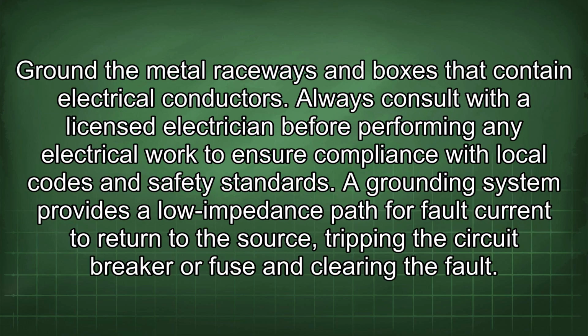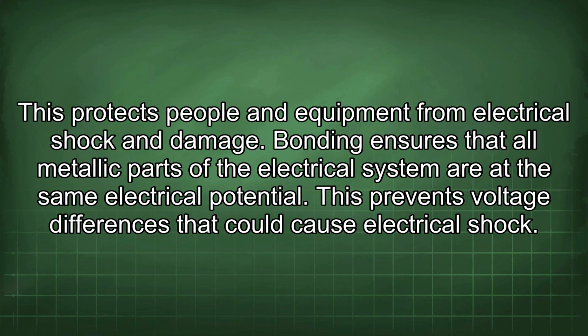Some additional notes to consider are to use anti-corrosion compound on all grounding connections to prevent corrosion. Ground the metal raceways and boxes that contain electrical conductors. Always consult with a licensed electrician before performing any electrical work to ensure compliance with local codes and safety standards. A grounding system provides a low impedance path for fault current to return to the source, tripping the circuit breaker or fuse and clearing the fault. This protects people and equipment from electrical shock and damage.